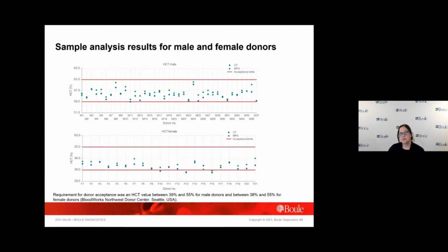In a study performed at Bloodworks Northwest Donor Center in Seattle, USA, the MPA and open tube sampling methods of Medonic M32 were compared in assessments of female and male adult donors. Sample analysis showed no male donors outside of limits with either the open tube or MPA method. For female donors, 3 samples were observed outside of limit with the open tube method, of which 2 were observed outside of limits also with the MPA method. The 3rd sample, which was outside of limit with the open tube, was observed close to limit with the MPA method. These results indicate good agreement between the MPA and open tube sampling methods. It shall be noted, however, that operator skills play an important role in analysis of capillary blood.